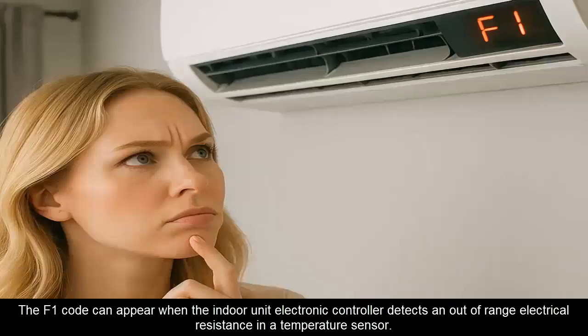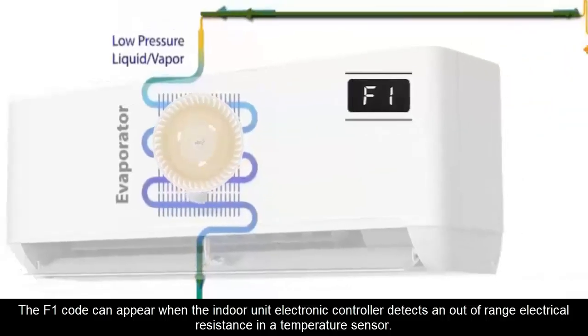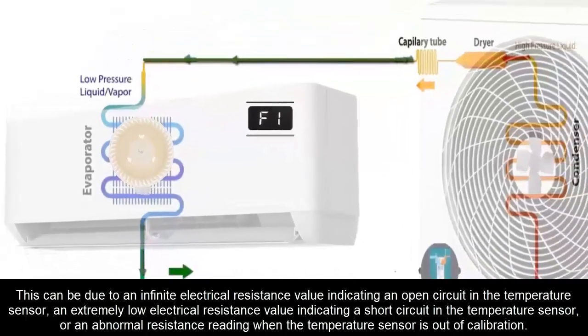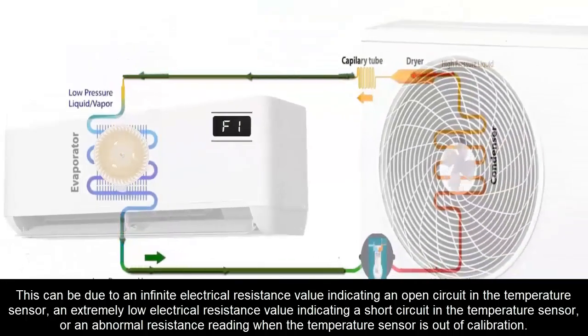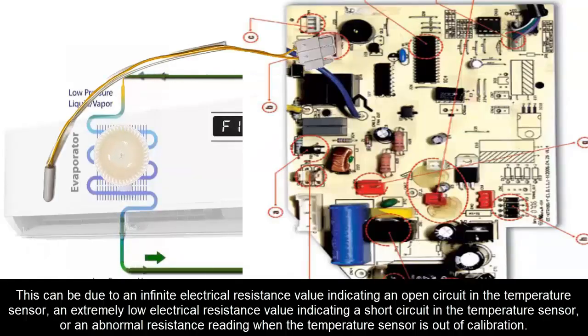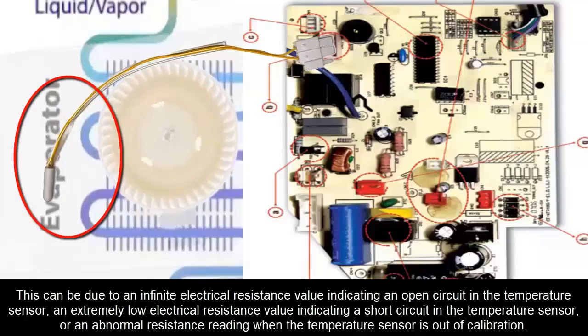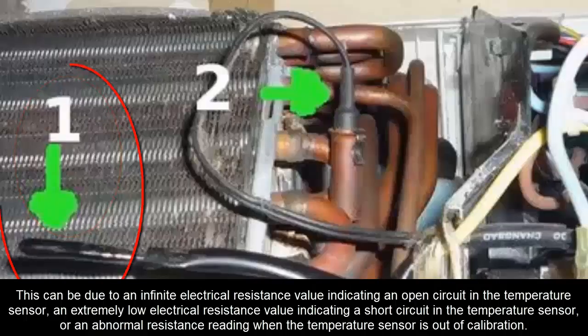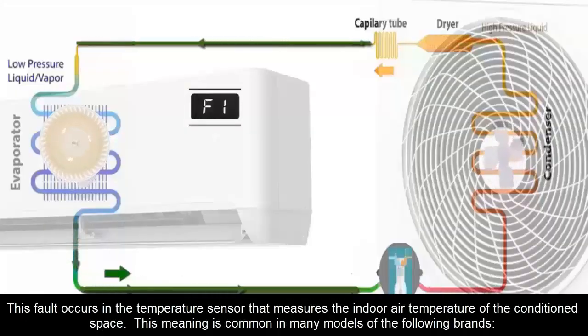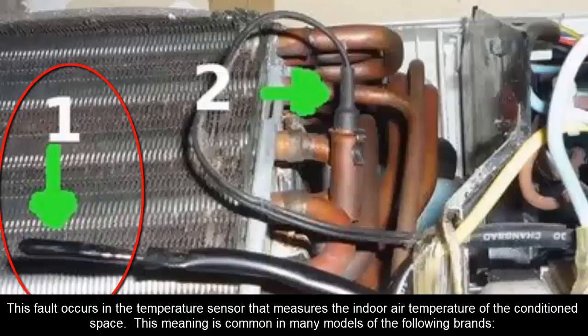The F1 code can appear when the indoor unit electronic controller detects an out-of-range electrical resistance in a temperature sensor. This can be due to an infinite electrical resistance value indicating an open circuit in the temperature sensor, an extremely low electrical resistance value indicating a short circuit in the temperature sensor, or an abnormal resistance reading when the temperature sensor is out of calibration. This fault occurs in the temperature sensor that measures the indoor air temperature of the conditioned space.